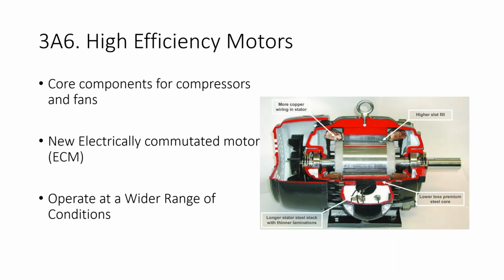High efficiency motors. Motors are the main component of any air conditioning system. In a centralized heating plant, we have more than 500 motors in our plant, and motor efficiency is a must. Those motors run continuously 24/7, and even a one-digit efficiency increase sums up to huge benefits at the end of the year. Motor technology has gotten better and better over time, and we now have electronically commutated motors, which can be controlled by our variable speed drives, and they can run across a wide range of conditions, on a low load and on a high load, with a minimum amount of energy.